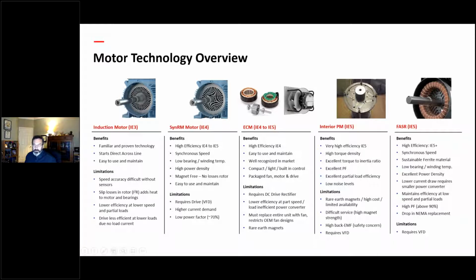But it is a synchronous reluctance motor. So it runs at synchronous speed, and it has magnets, so it won't run across the line, and it does require a variable speed drive. So that's still a disadvantage over maybe induction that'll run across the line. So that's all the technologies out there. We're kind of focusing on this one next, on the technology.